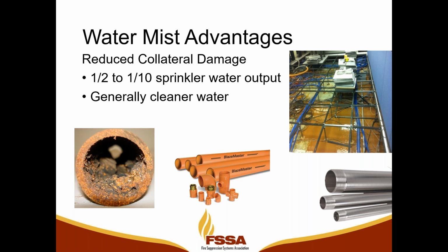When we're talking about a sprinkler system, we're typically using black pipe, and black pipe's got a little rougher surface than some of the other pipes, and it can lead to a buildup of bacteria, kind of think in terms of a bacterial sludge that over time can corrode the pipe and cause pinhole leaks or cause a whole section of pipe to fail and have to be replaced. And you can imagine what that water might be like when it comes out. Now, granted, on a sprinkler system, maybe we're not as concerned because we're not necessarily trying to protect the contents of that space. We're just trying to preserve the structure long enough for people to get out of it.